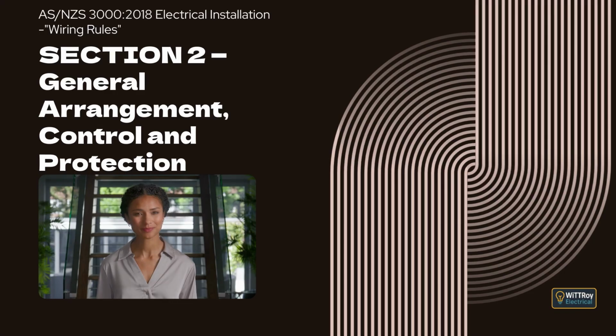2.3.3.4 Location and operation. Main switches must be placed where people can reach them easily in an emergency. They must not be mounted too high. The operating handle must be no more than 2 meters above the floor or any safe platform nearby. There is one exception. A main switch does not need to be accessible if the switchboard is on public land and the installation is protected by other safety measures. Examples include telephone cabinets, traffic control equipment, or bus shelters.